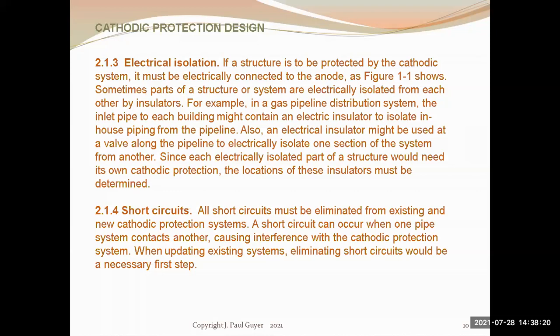And you need to have electrical isolation. You need to have drawings or other information to assure you that your protected structure is electrically isolated from anything else. The approach you often take, for example with a pipeline, is that you chop the pipeline up into finite lengths, 50 feet long, 100 feet long, whatever. And then you put electrically isolating flanges in the pipeline. And then the next element in the protected structure is attached.